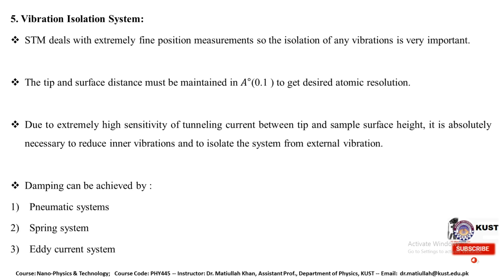So the fifth portion of the scanning tunneling microscope is the vibration isolation system, because STM deals with extremely fine position measurement. So the isolation of any vibration is very important. The distance between the tip and the surface of the sample must be maintained at around 0.1 angstrom to get the desired atomic resolution.